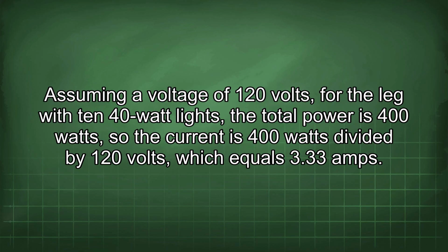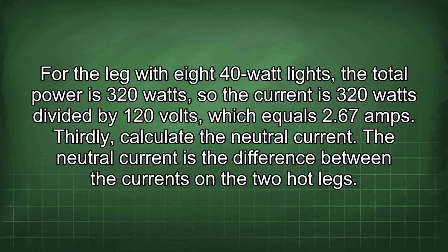Assuming a voltage of 120 volts, for the leg with 10 40-watt lights, the total power is 400 watts, so the current is 400 watts divided by 120 volts, which equals 3.33 amps. For the leg with 8 40-watt lights, the total power is 320 watts, so the current is 320 watts divided by 120 volts, which equals 2.67 amps.